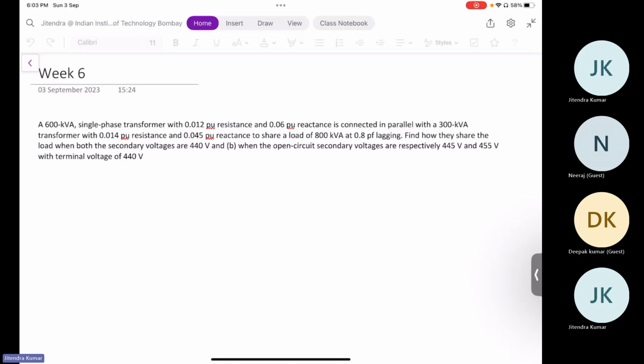And another thing is that it is economic. It is economic to install another transformer in parallel rather than replacing it with a larger unit. Also, if reliability is our concern, because in transmission lines or in the operation of the transformer, reliability is the major thing that everybody is concerned about, because if a transformer got tripped, then you don't want to stop all of your work. In that case, at least a partial fraction of the load should be supplied from somewhere, and in those cases, multiple transformers help. Okay, so these were the basic idea behind it, and there are certain conditions to satisfy for the successful operation of transformers connected in parallel.